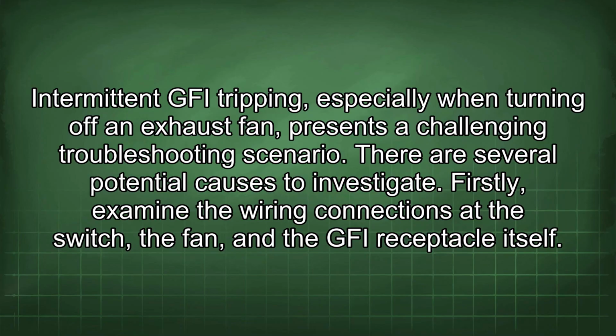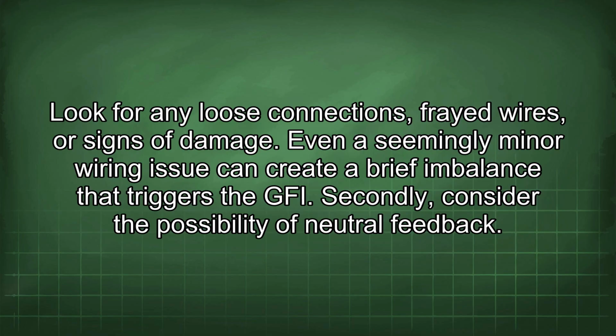Intermittent GFI tripping, especially when turning off an exhaust fan, presents a challenging troubleshooting scenario. There are several potential causes to investigate. Firstly, examine the wiring connections at the switch, the fan, and the GFI receptacle itself. Look for any loose connections, frayed wires, or signs of damage. Even a seemingly minor wiring issue can create a brief imbalance that triggers the GFI.